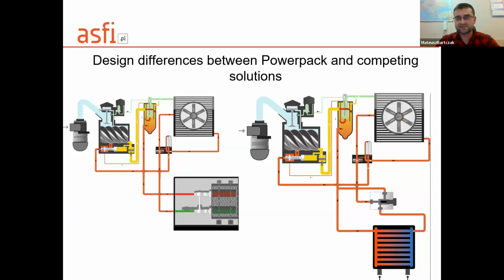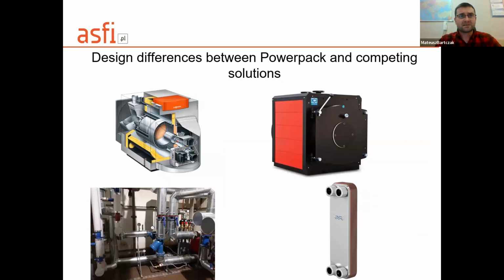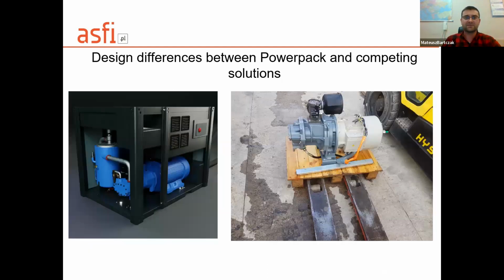So, a kind of summary. We have a large exchanger with a low pressure drop. We don't have an oil three-way valve, and no pressure drop connected with it. We have a circulation pump as the energy recovery executive element, a PLC controller with a power control algorithm, and a temperature sensor. So we have a complete heating device and the right heat exchanger in the box. So power pack and power control are a fully functional heating device. The exchanger in a compressor is just one element that can create a system, just like a boiler without a burner, or a burner without automation.